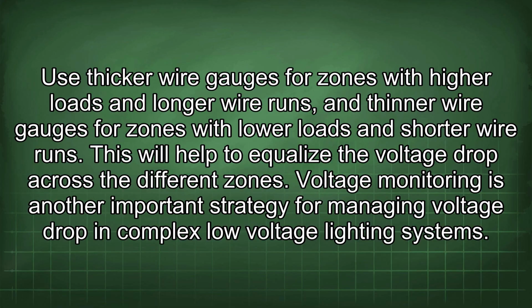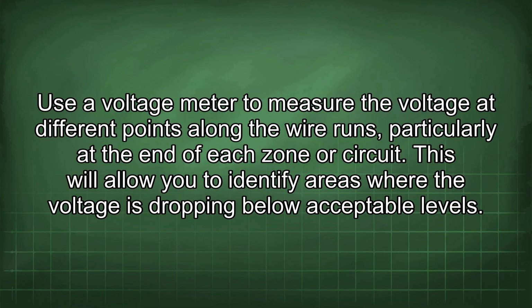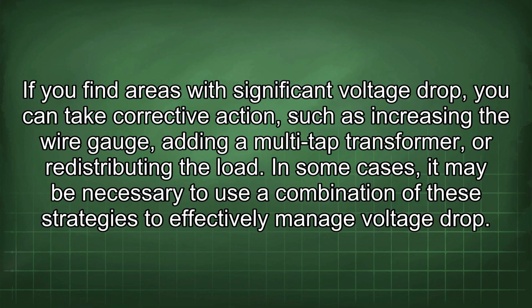Voltage monitoring is another important strategy for managing voltage drop in complex low-voltage lighting systems. Use a voltage meter to measure the voltage at different points along the wire runs, particularly at the end of each zone or circuit. This will allow you to identify areas where the voltage is dropping below acceptable levels. If you find areas with significant voltage drop, you can take corrective action, such as increasing the wire gauge, adding a multi-tap transformer, or redistributing the load.